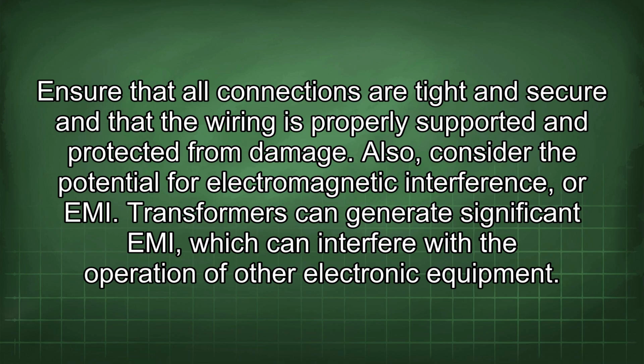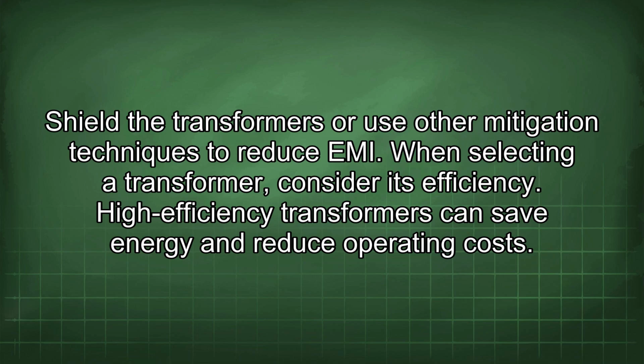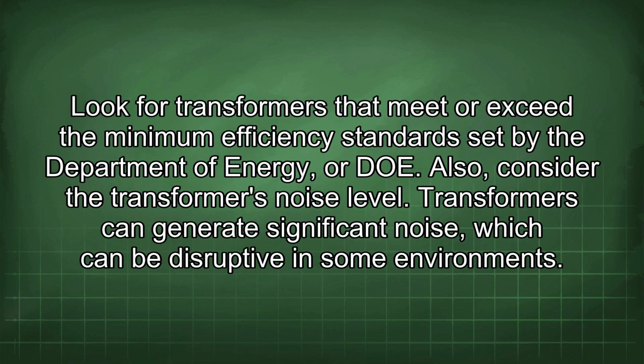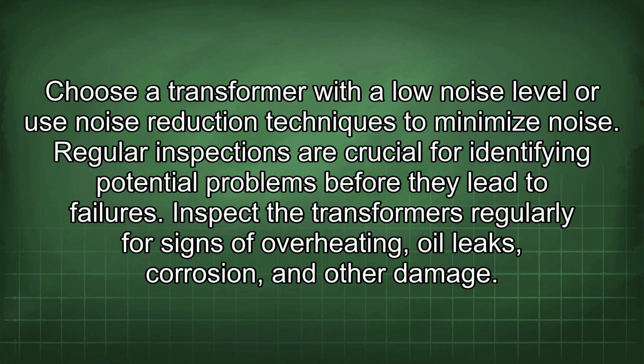Also, consider the potential for electromagnetic interference, or EMI. Transformers can generate significant EMI, which can interfere with the operation of other electronic equipment. Shield the transformers or use other mitigation techniques to reduce EMI. When selecting a transformer, consider its efficiency. High-efficiency transformers can save energy and reduce operating costs. Look for transformers that meet or exceed the minimum efficiency standards set by the Department of Energy, or DOE. Also, consider the transformer's noise level. Transformers can generate significant noise, which can be disruptive in some environments. Choose a transformer with a low noise level or use noise reduction techniques to minimize noise.